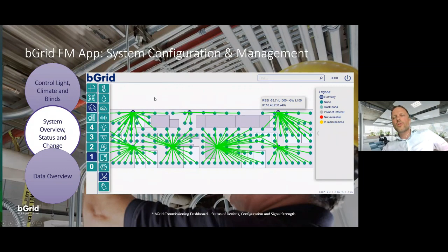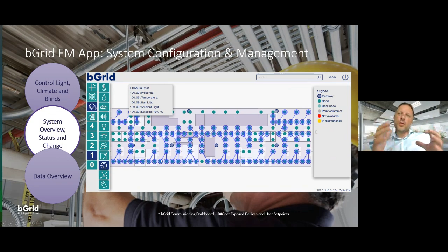We can also see the conditions of our signal strengths, so here you see the gateways and the nodes - if they're green, they're good, if orange, still working but getting trickier, and red is not good. We can also see the BACnet configuration. For example, I have 3 nodes connected under one BACnet, like 101.09, and if you hover over it you can see which node reports which values to the BACnet value. This also allows us to change the clustering of control loops without having to change anything in the BMS.